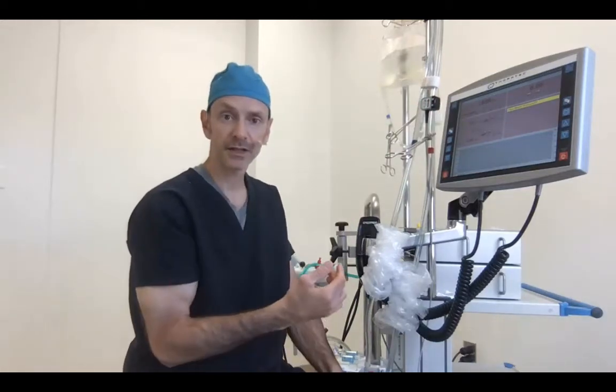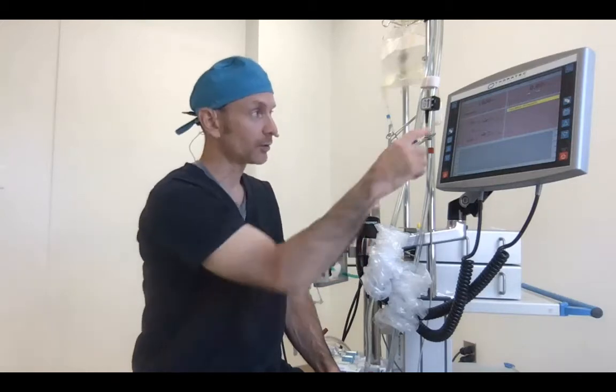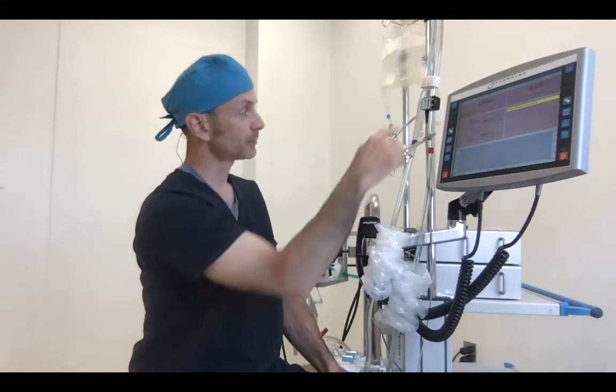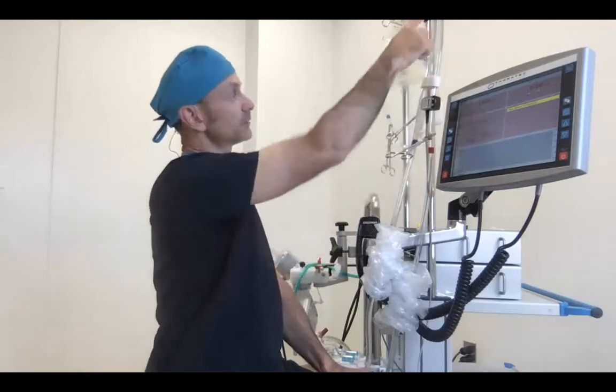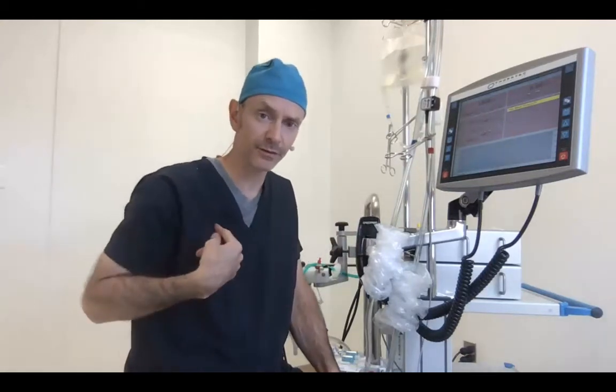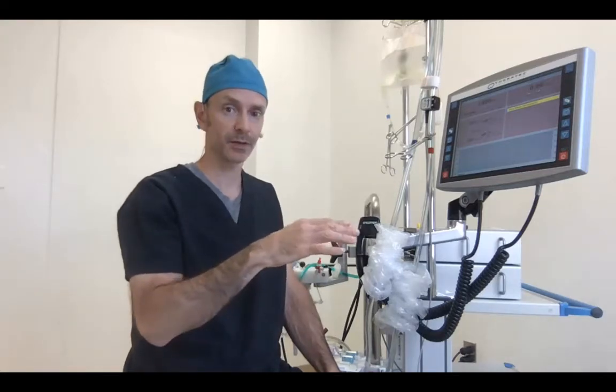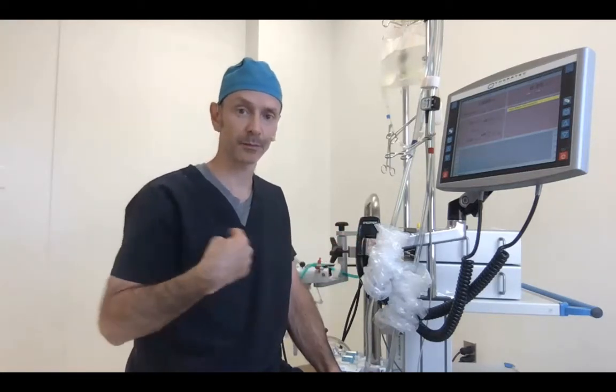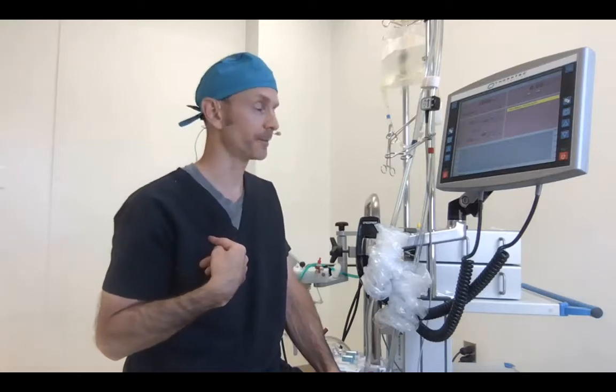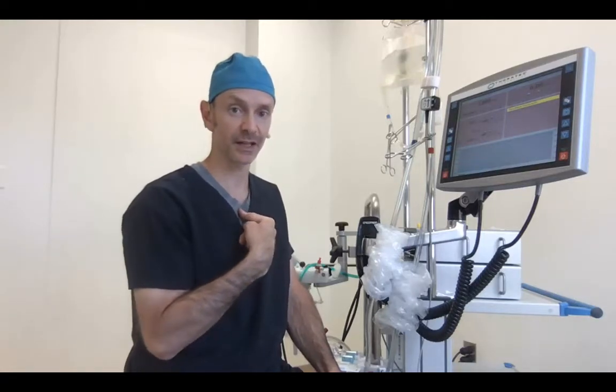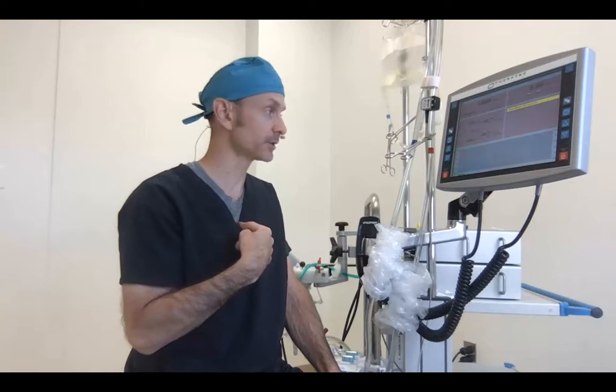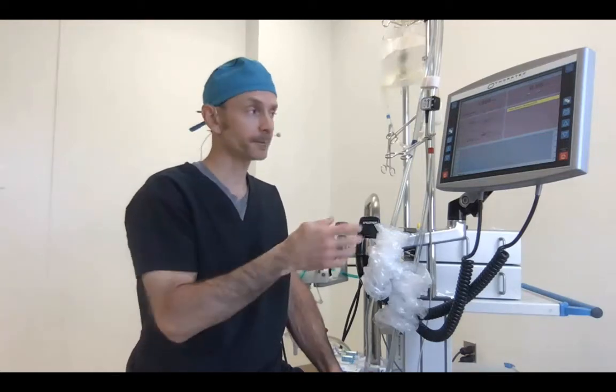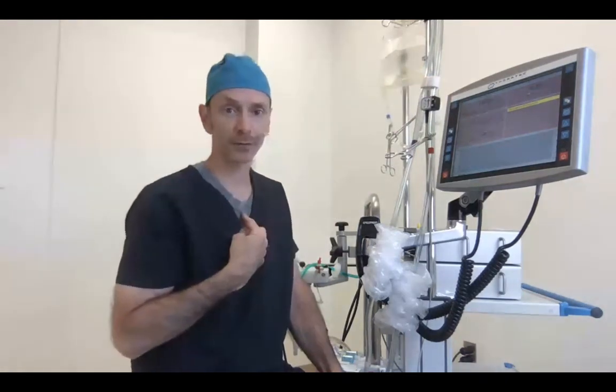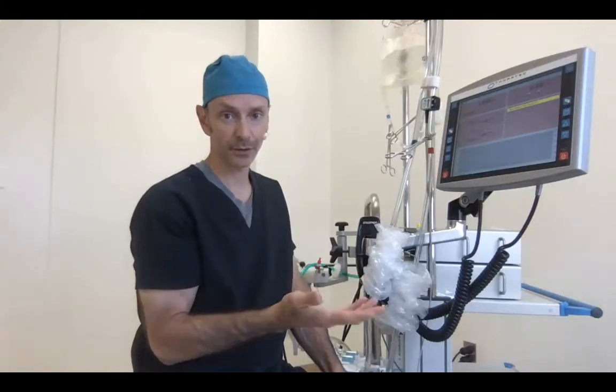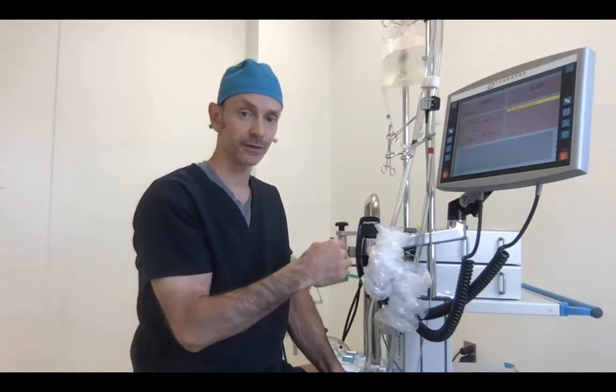And of course, you should understand that that would be a much lower pressure and lower RPMs if you're initiating VV ECMO, because this arterial cannula would be connected all the way over to a vein if you're doing VV ECMO. So it's going to be the height of the table, which is the column of fluid, the height of the table, and the patient's CVP that you're trying to overcome. But if you're doing VA ECMO and the cannula is in the aorta or arterial branch, then it's going to be the height of the table and the patient's arterial blood pressure. So you'd need greater RPMs to initiate VA than you do for VV.